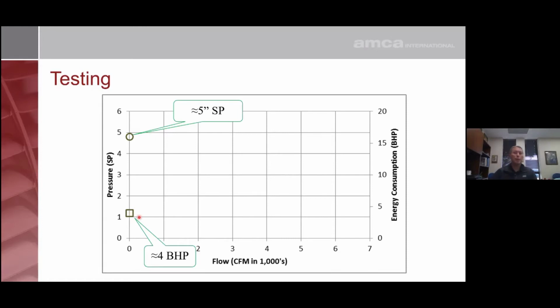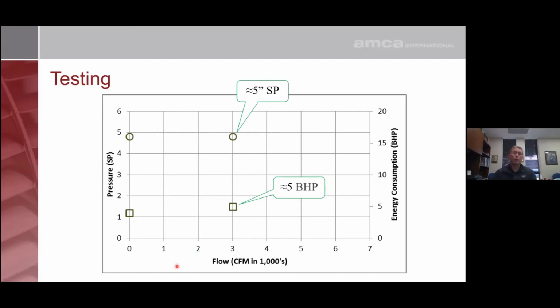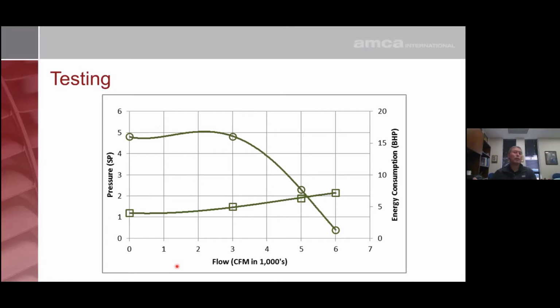And we just open up the nozzles, record the work that the fan's doing until we have enough points to create a curve. Now, we only have 4 points here. Typically, when we're testing a fan, it's anywhere between 8 to 12 points in order to get a little bit more accurate fan curve.